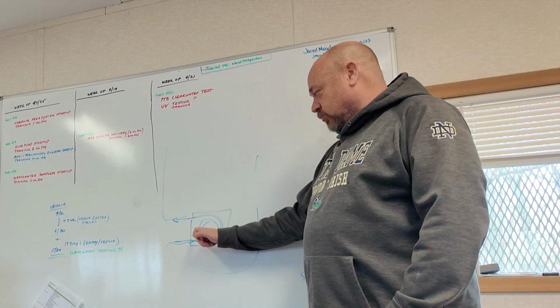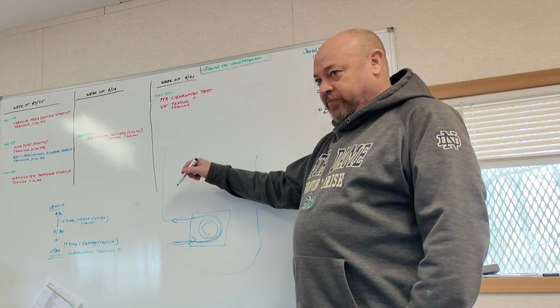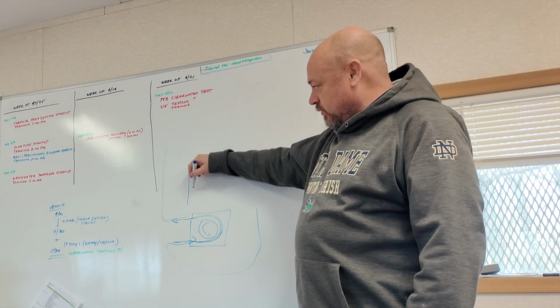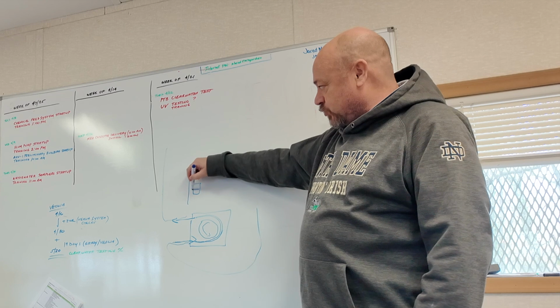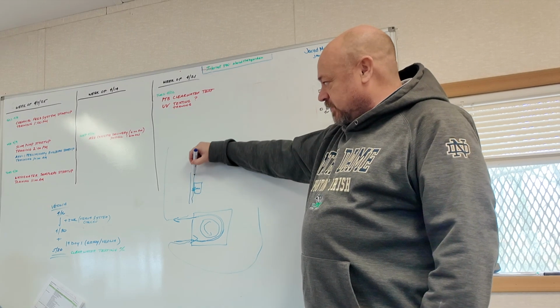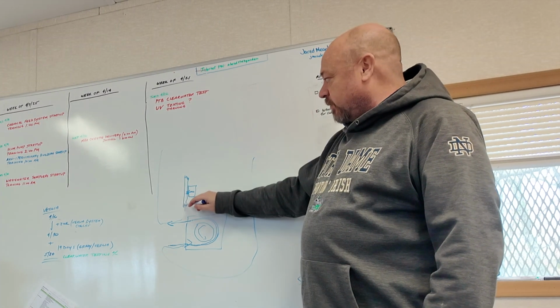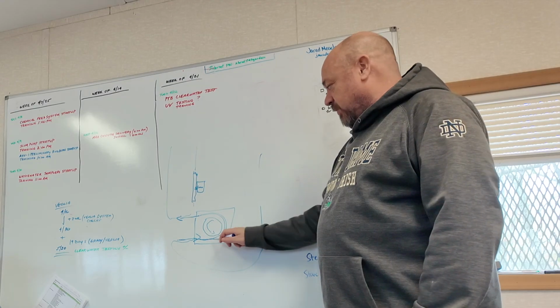What makes this style pump different than a lot of the other ones, the chemical is actually on the inside of this tubing. Other style pumps that they call diaphragm pumps, the chemical is coming through the head and you have basically a diaphragm that pushes back and forth, and the chemical is basically inside the pump head. So it's coming from the bottom and going out the top. This is just basically a roller.